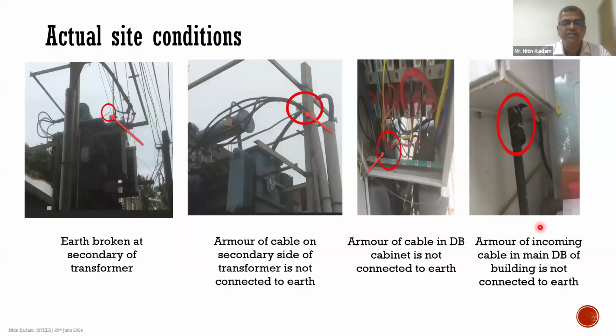These are some of the other pictures which I've seen. The earth is broken on the secondary of the transformer here. So if somebody is thinking that on the elevator installation in the building there is an earth which is coming, maybe only that end of the cable is connected, but there is actually an earthing wire which is broken on the transformer which is supplying the building installation. The armor of the cable is not connected at all. The same you can see in this picture. And in fact, in this picture, you see the armor is insulated.